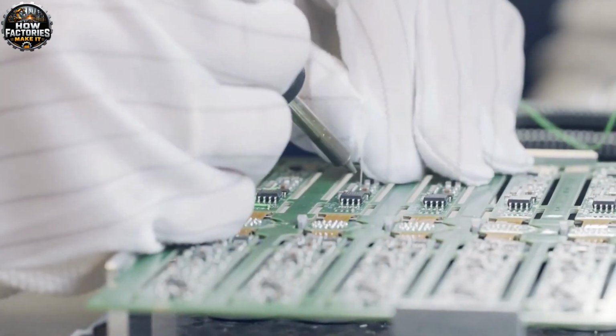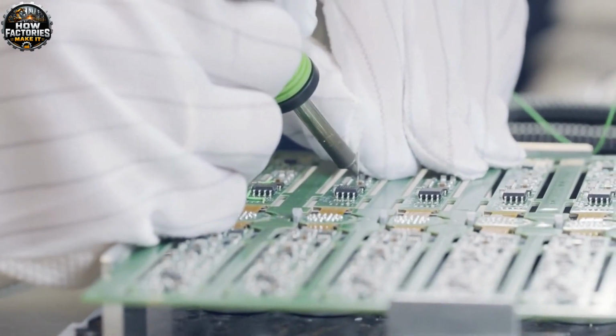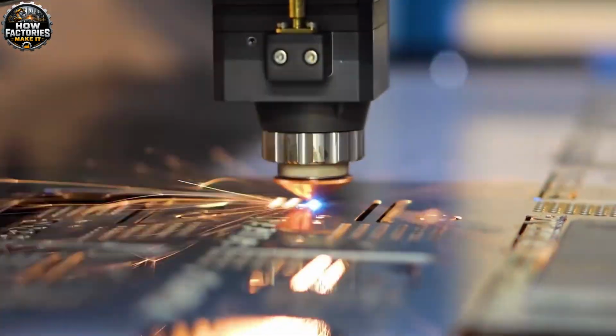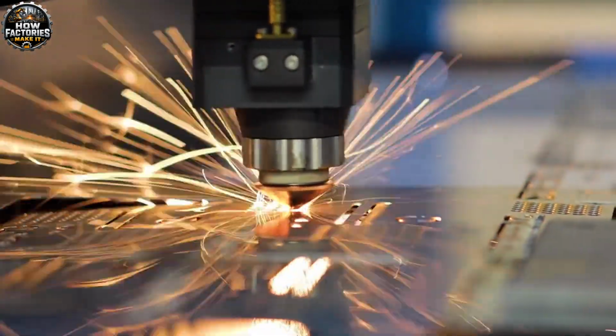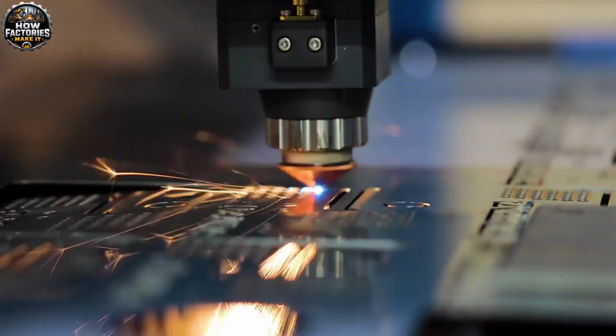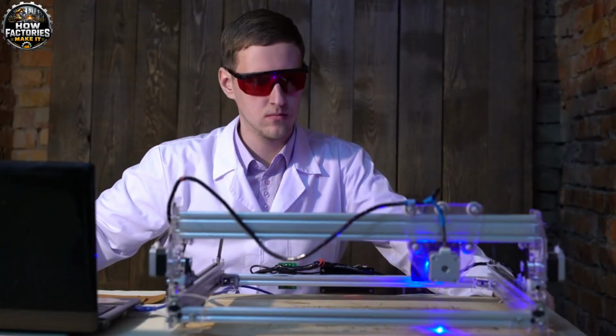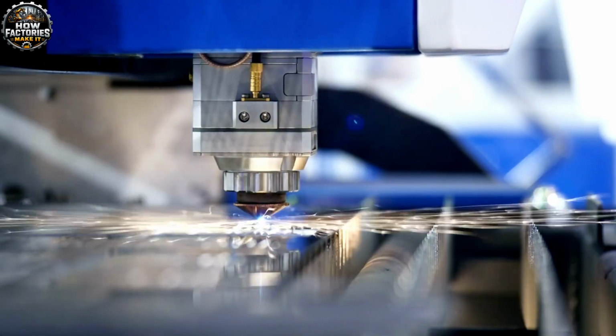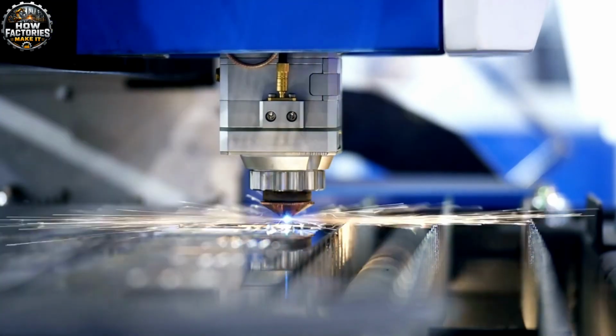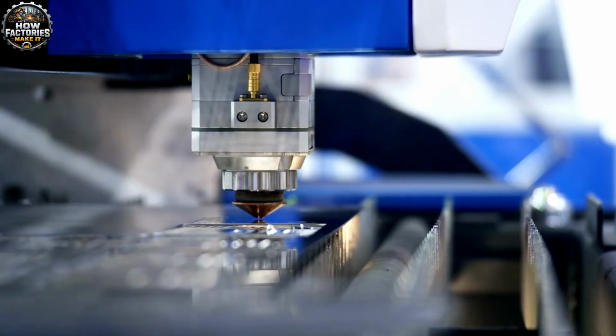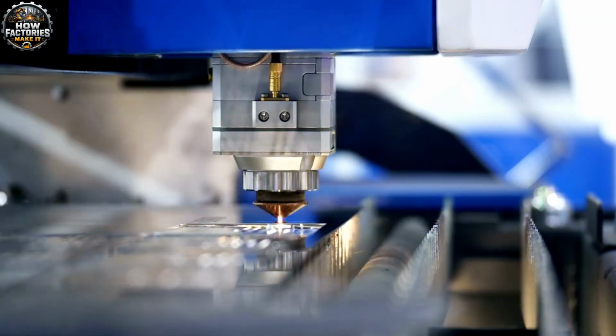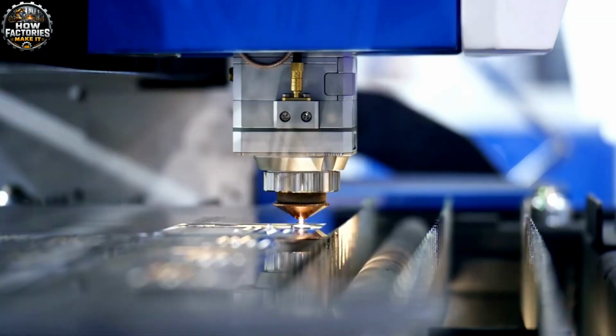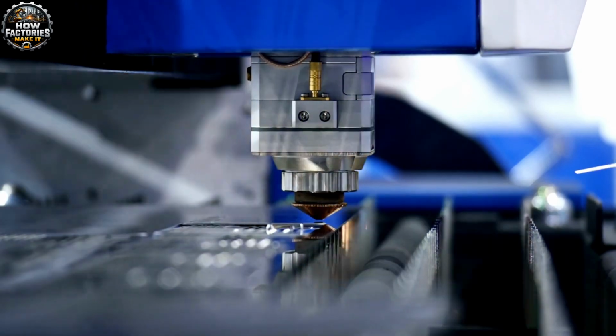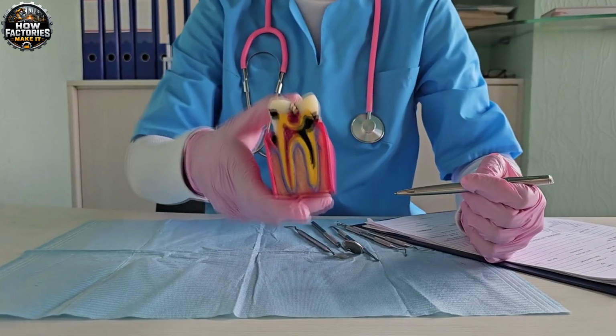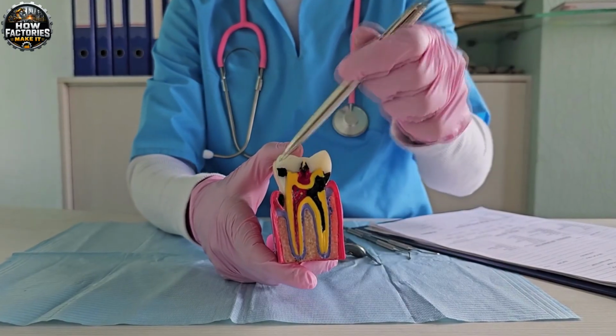Precision welding equipment joins the housing components. Laser welding may be used because it creates a narrow, controlled seam with limited heat exposure. The enclosure is then checked for microscopic leaks. A helium leak test can reveal openings too small to detect visually. The sealed unit may also be submerged in controlled solutions and monitored over time to determine whether moisture can penetrate the housing. Only implants that remain sealed and electrically stable move to the next stage.